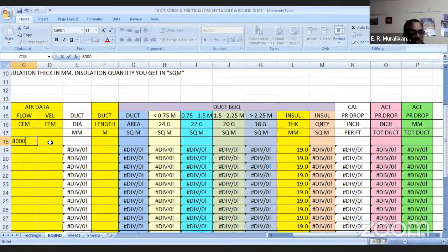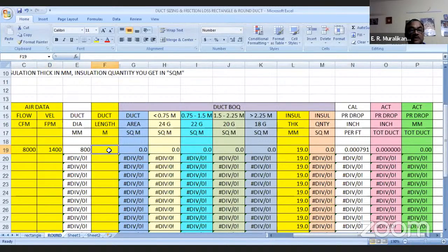Now CFM I put here, say 8000 CFM, and FPM 1400, and duct length I put say 13 meters. It comes to 22 gauge because it is more than 750, 22 gauge, and 1.98 is the friction loss. I put here 1000, it comes to 0.83. I put here 700, 0.32. So this is how it actually varies.